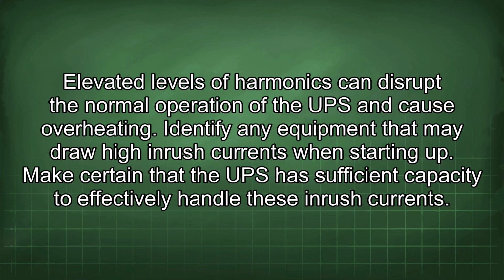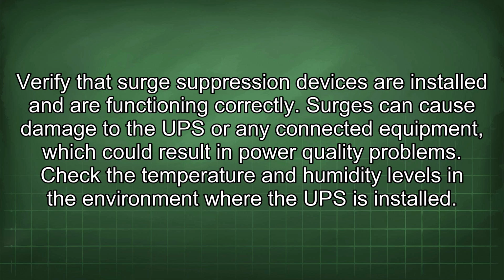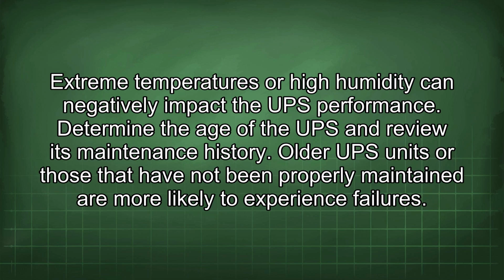Identify any equipment that may draw high inrush currents when starting up. Make certain that the UPS has sufficient capacity to effectively handle these inrush currents. Verify that surge suppression devices are installed and are functioning correctly. Surges can cause damage to the UPS or any connected equipment, which could result in power quality problems. Check the temperature and humidity levels in the environment where the UPS is installed. Extreme temperatures or high humidity can negatively impact the UPS performance.